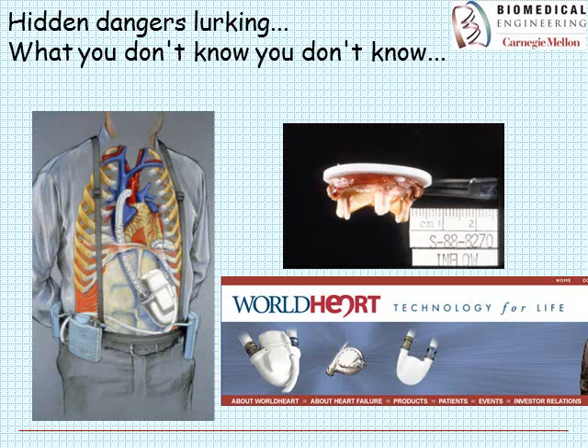Early in the artificial heart program at the University of Pittsburgh, we began implanting a new device known as the Novacor. Very soon, around the second or third patient, it became evident this device was generating a horrendous blood clot around one of the valves, jeopardizing the entire program and even the survival of the company. This was despite years of development, animal testing, bench testing, and hazard analyses — it was an unexpected and catastrophic outcome.